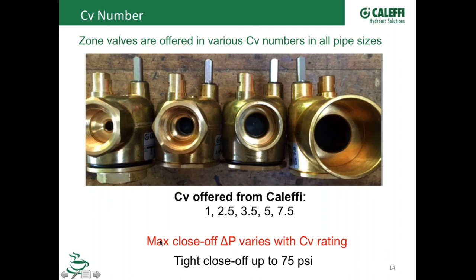So yeah, Bob, I was just going to say that this is a topic that comes up pretty regularly. In each of our sizes of valves and different connection types, we offer multiple CV values, and you're 100% correct that you want to make sure you're choosing the right one. The other thing that comes up real regularly is people think that when we list our zone valves in our catalog based on their max differential pressure, that's the maximum pressure they can have in the system, as far as static pressure.